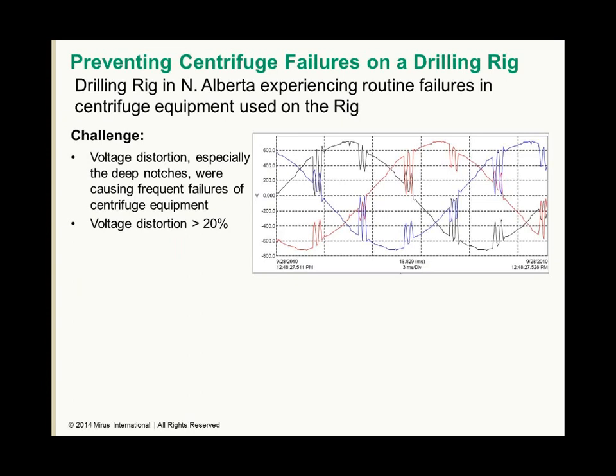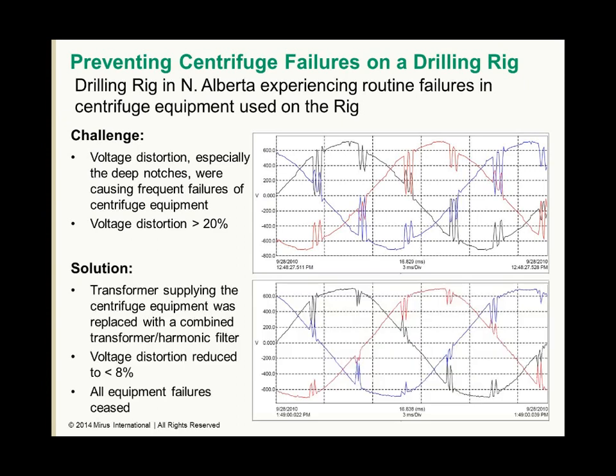This example shows a land-based rig in northern Alberta where the high levels of voltage distortion were causing the AC drives on centrifuge equipment to fail very quickly. All equipment failures ceased after application of the filter. You still can see that there's distortion on the waveform, and this is due to the thyristor bridges on a lot of the drilling equipment.